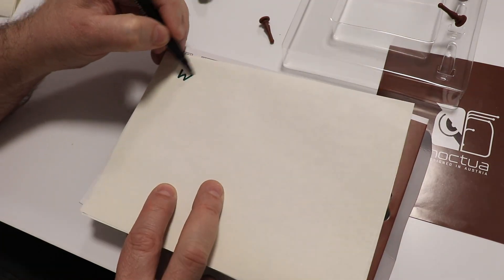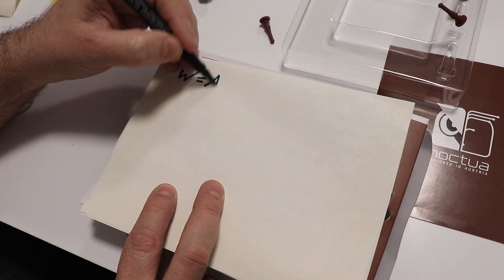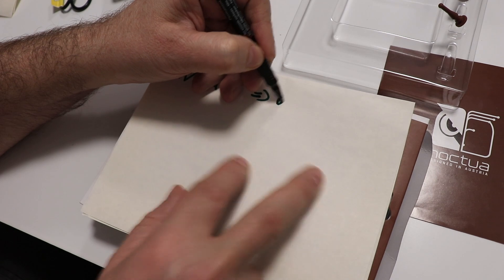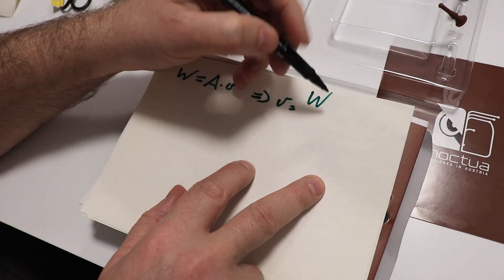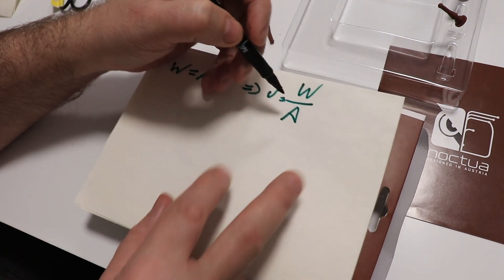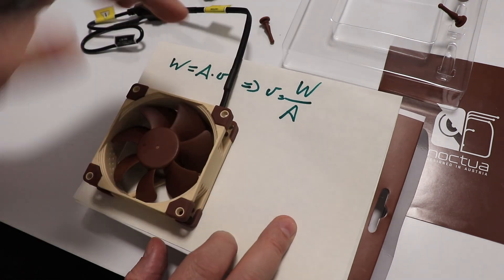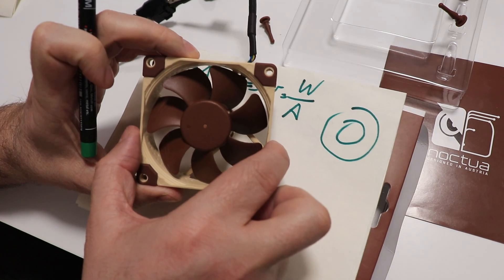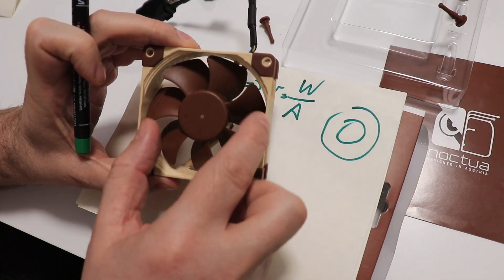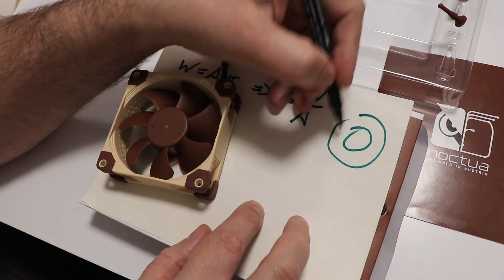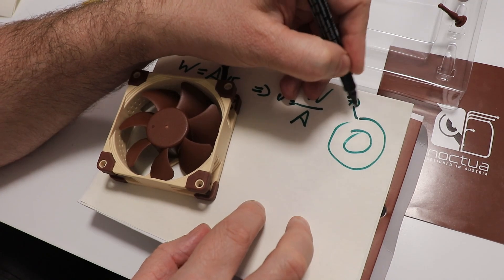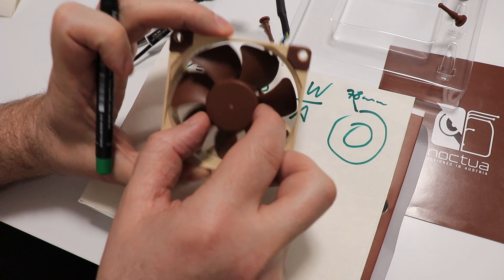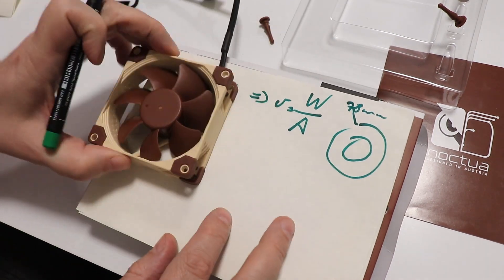Now the cubic flow rate equals area multiplied by velocity. So from this, the velocity equals cubic flow rate divided by area. Now the area is actually some kind of ring. This is 80 millimeters, well actually a little bit smaller. So let's say 78 millimeter is the outer diameter. And the inner ring, inner circle, inner diameter is approximately 30 millimeters.